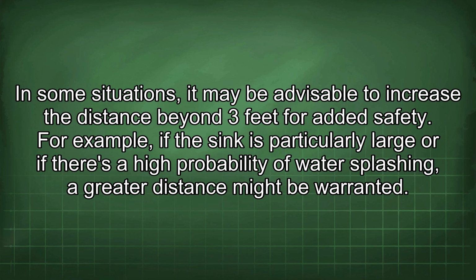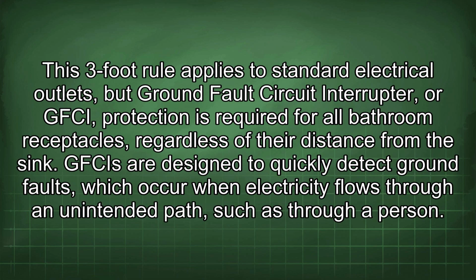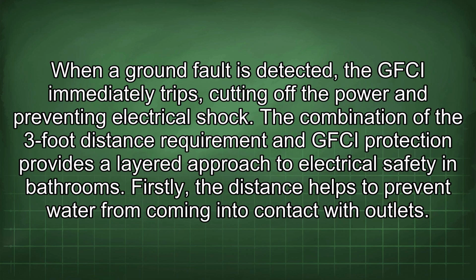In some situations, it may be advisable to increase the distance beyond 3 feet for added safety. For example, if the sink is particularly large or if there's a high probability of water splashing, a greater distance might be warranted. This 3-foot rule applies to standard electrical outlets, but ground fault circuit interrupter, or GFCI, protection is required for all bathroom receptacles, regardless of their distance from the sink. GFCIs are designed to quickly detect ground faults, which occur when electricity flows through an unintended path, such as through a person. When a ground fault is detected, the GFCI immediately trips, cutting off the power and preventing electrical shock.